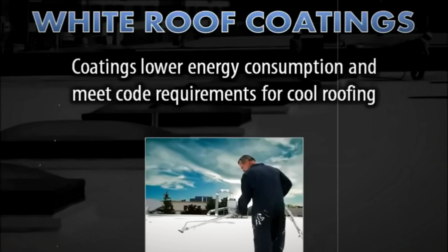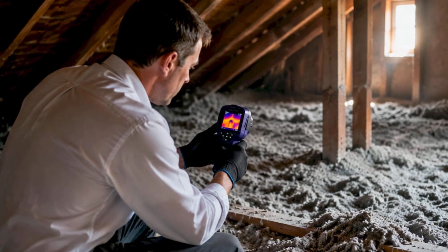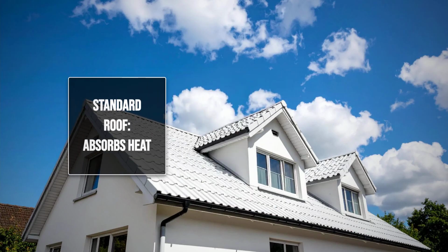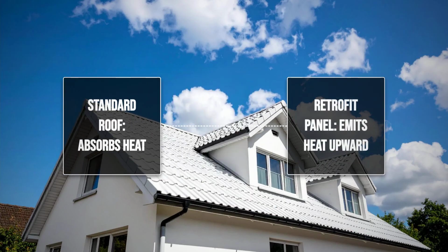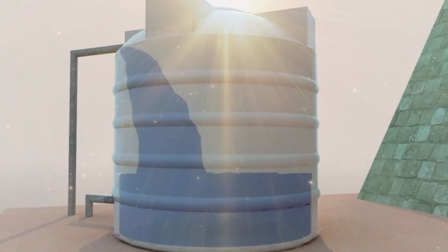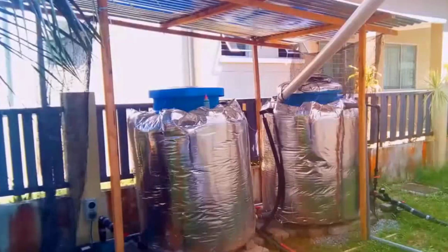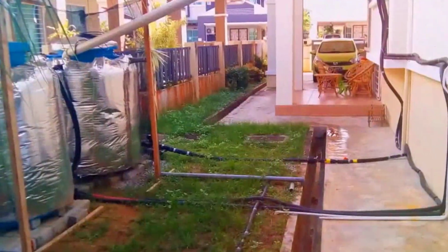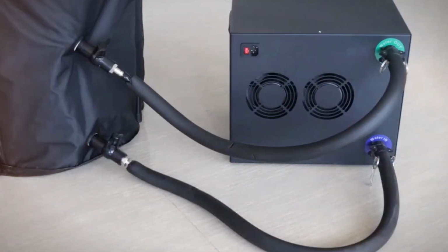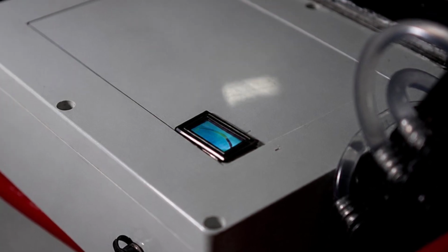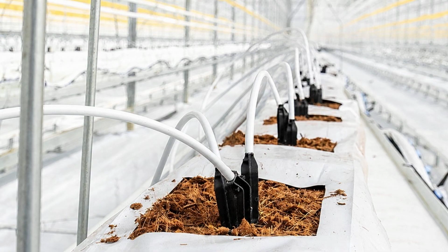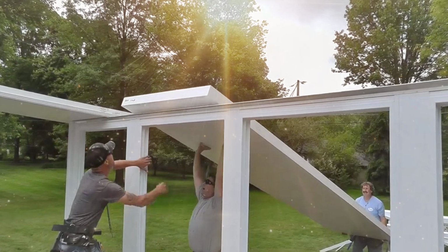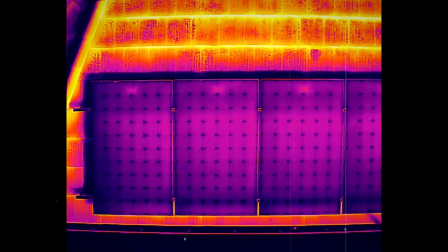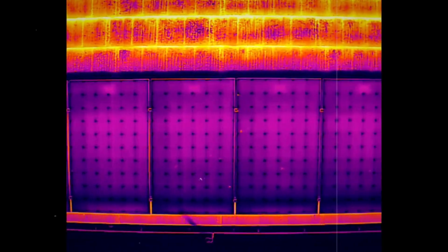We normally think of a roof as a surface that absorbs sunlight and transfers heat indoors. With the correct materials and design, part of that same roof could release heat upward instead. That creates several possible uses. A panel could cool water overnight and store it in an insulated tank for use the following afternoon. It could pre-cool the liquid entering a mechanical chiller. It could reduce the temperature of a battery enclosure, greenhouse, workshop, food storage room, or sleeping area. It could also be integrated into roofing materials so the building rejects more heat before the air conditioner ever turns on.